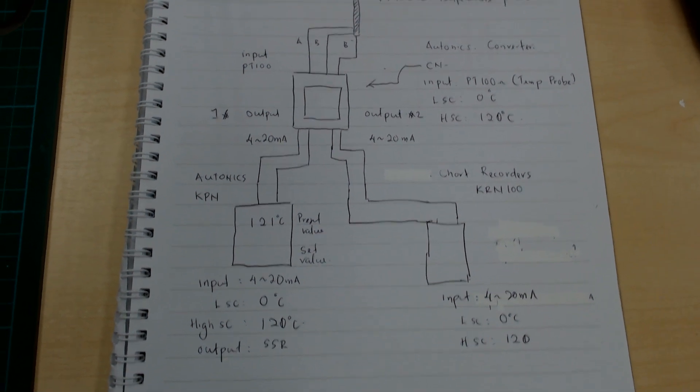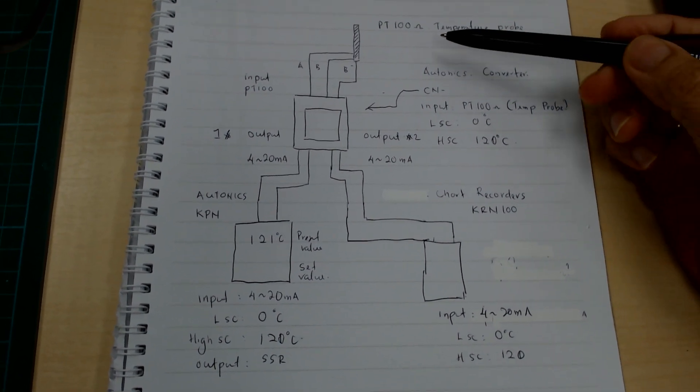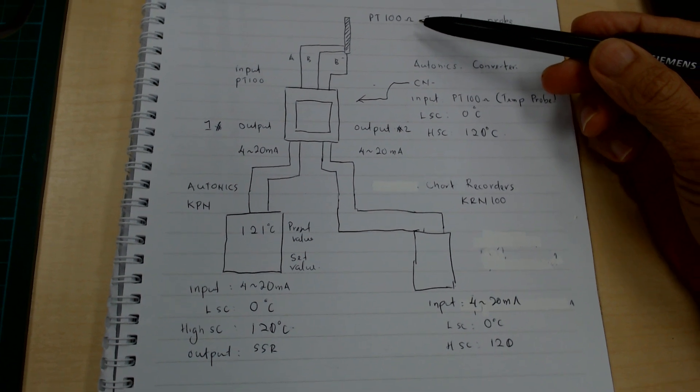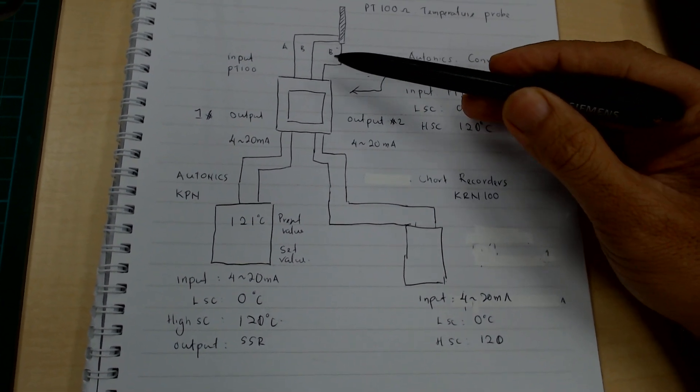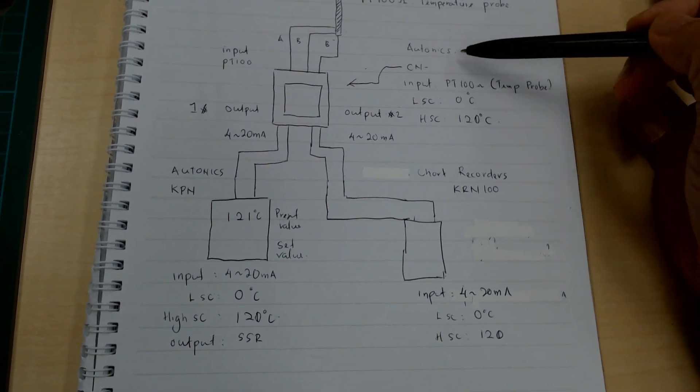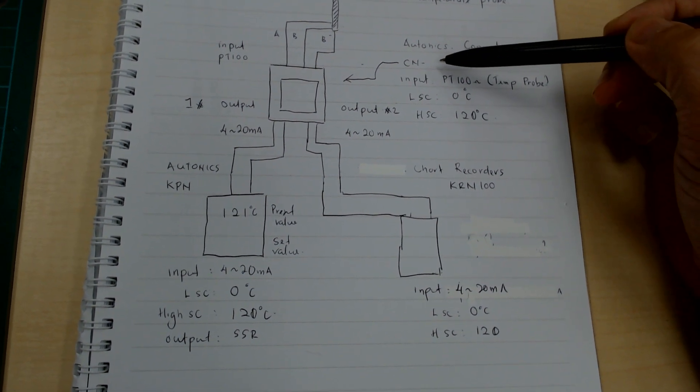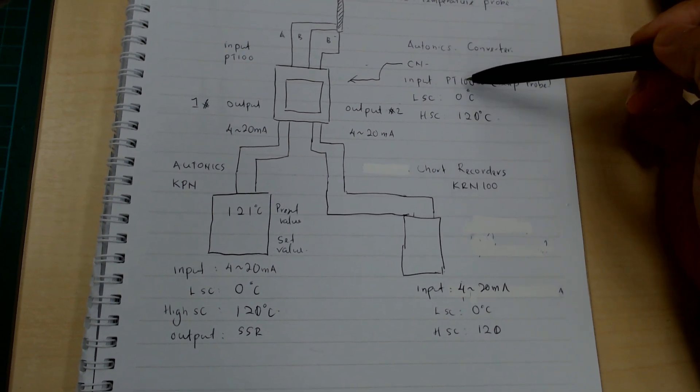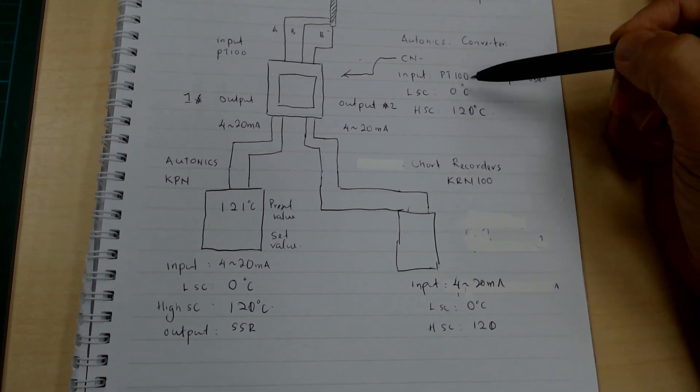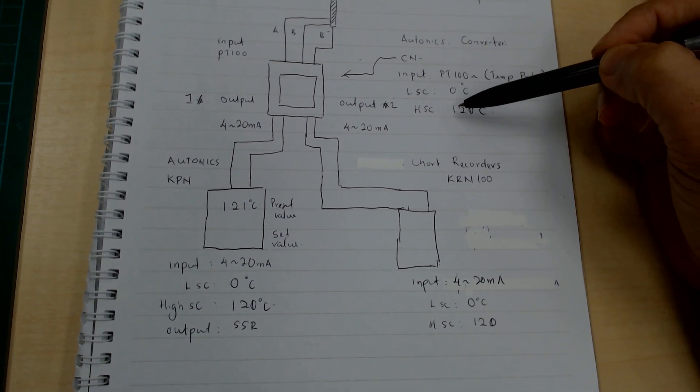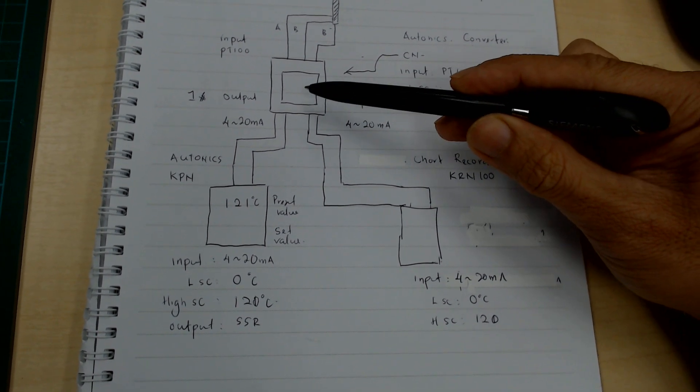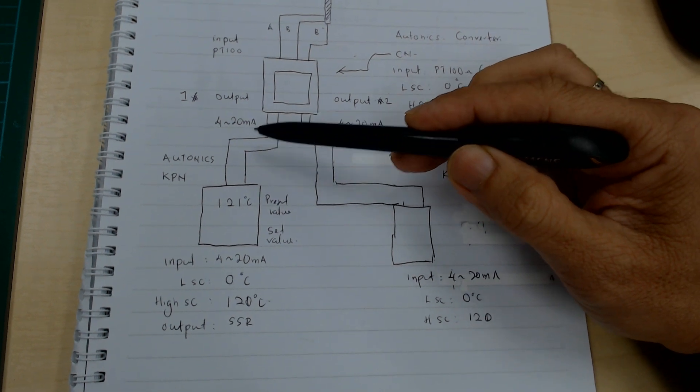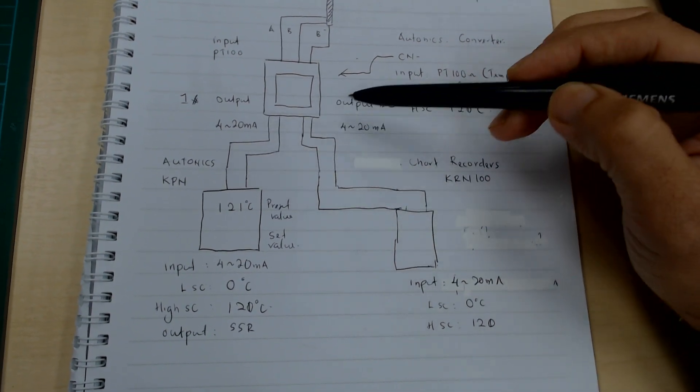Okay, now we have a converter. Our temperature probe is PT100 with three wire, the converter is CN6000. Input is PT100, setting temperature probe low scale zero Celsius, high scale 120 Celsius. The converter comes with two outputs. I use signal output 4 to 20mA, output two and output one.